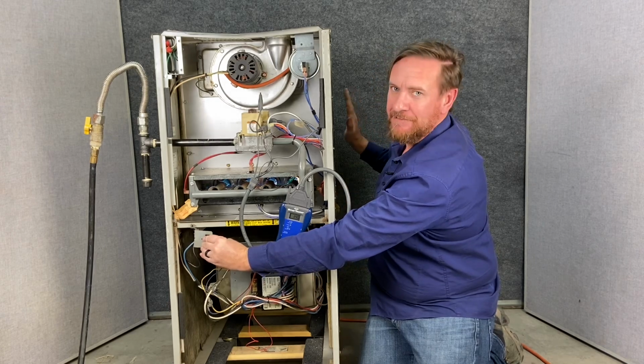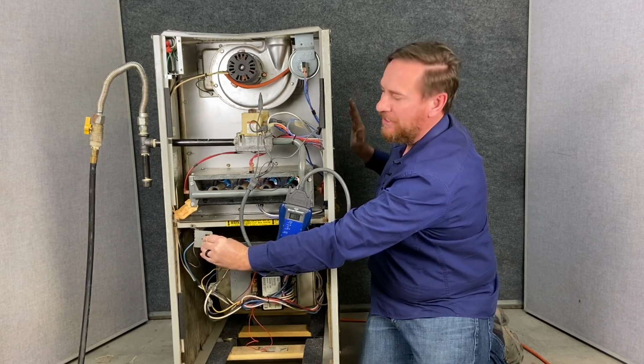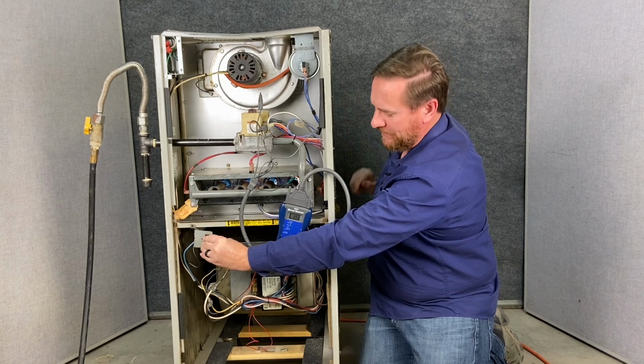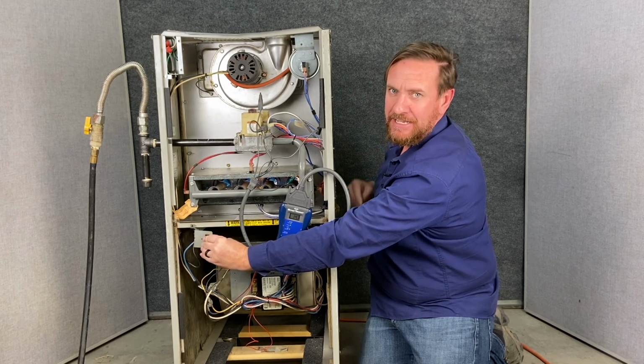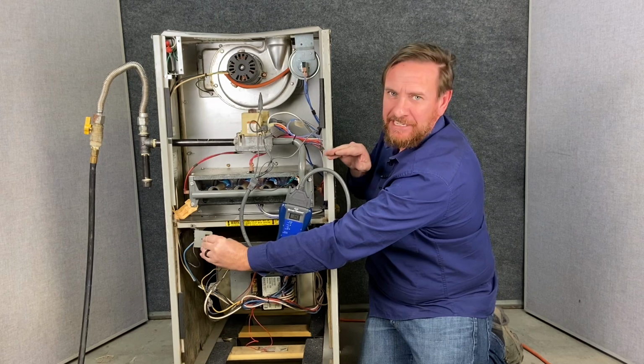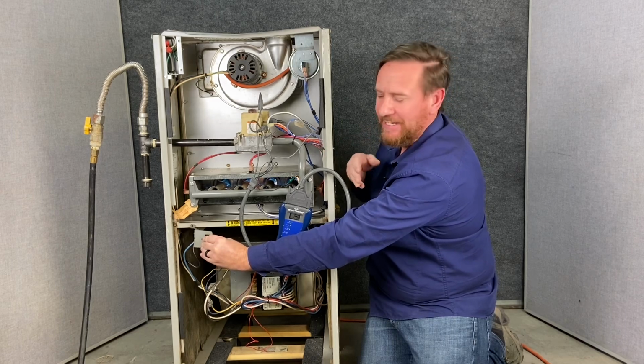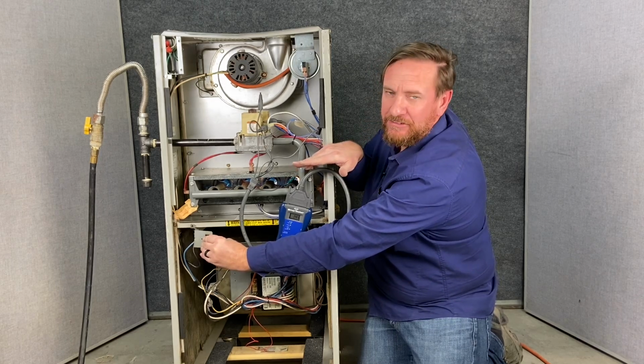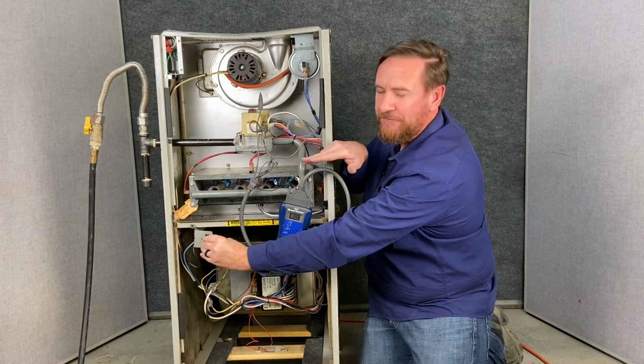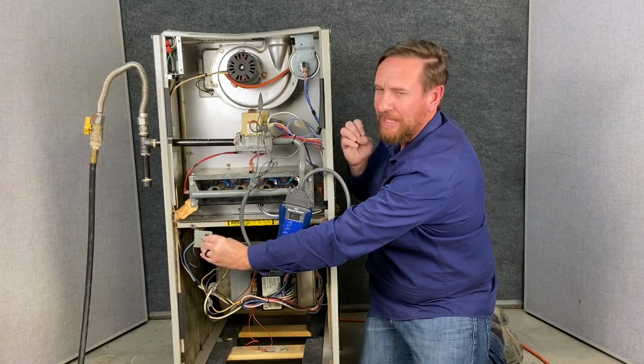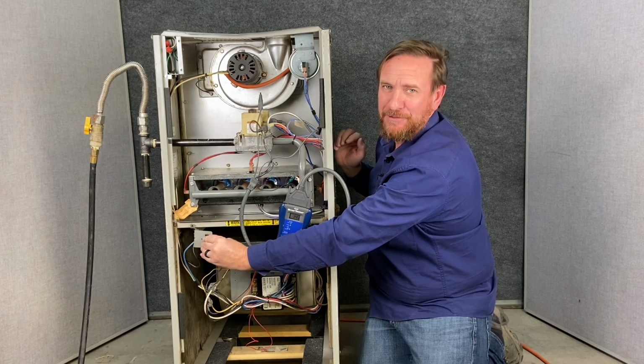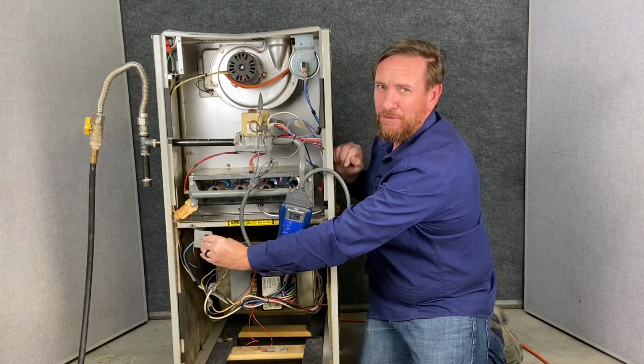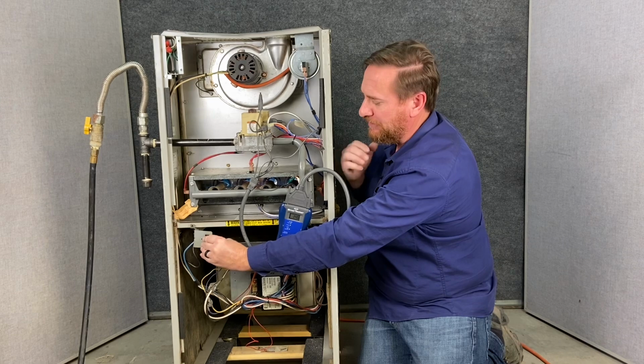I can feel the heat from the heat exchanger already because I have the side cut off. Once this heat exchanger gets warm enough, now anytime you're working with any gas furnace, you always want to stand to the side and then look in there once it starts up, but you never want to look into the front when it first starts. Those flames can roll out and they can burn your eyebrows, burn your beard, burn your hair, or worse, burn your eyes. So you want to make sure you're always standing to the side.